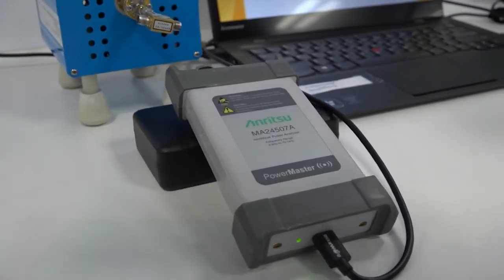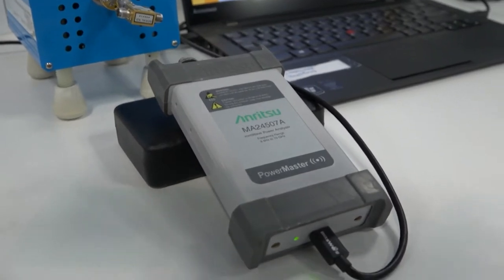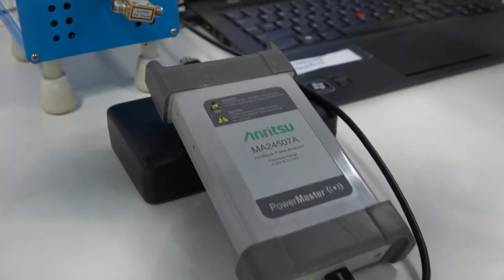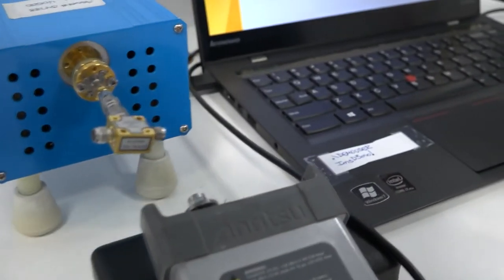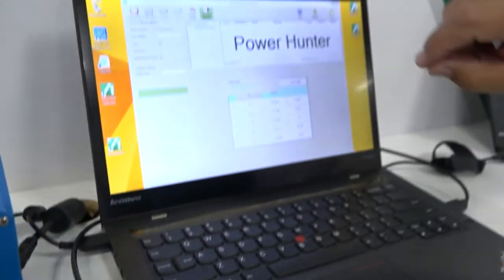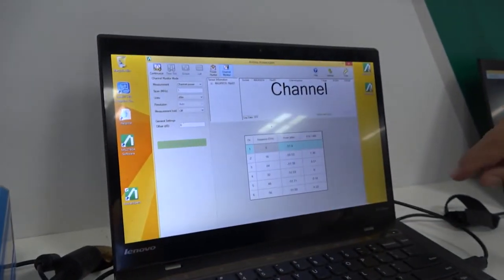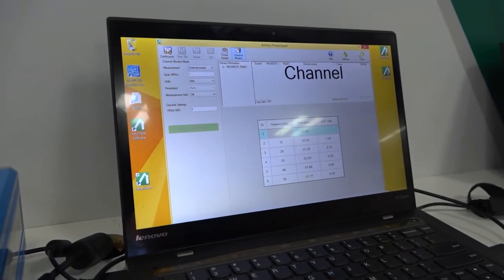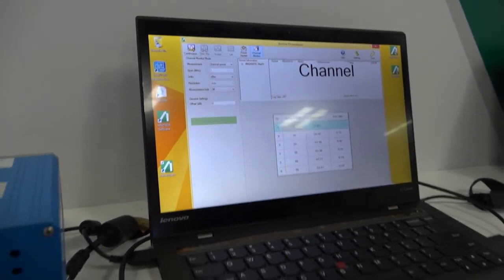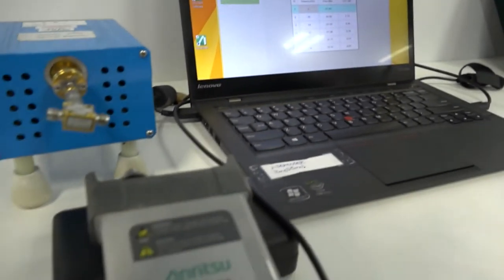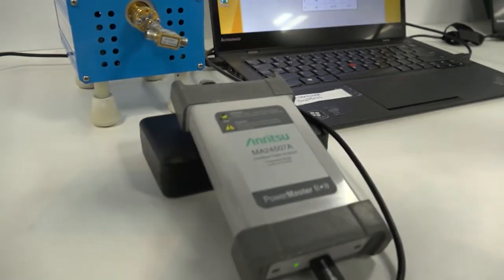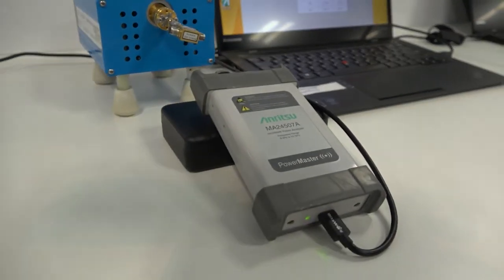Well, sometimes you want to make a power measurement at a specific frequency. So with a new feature called Channel Monitor, you can tell this power analyzer what specific frequencies you want to measure. For example, if you're measuring an amplifier, you may want to measure a fundamental and the harmonics.